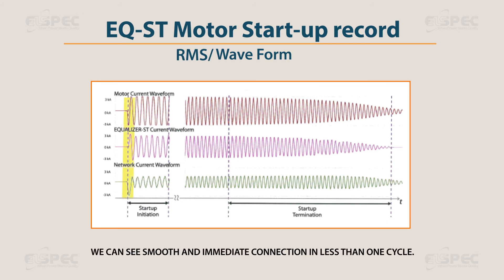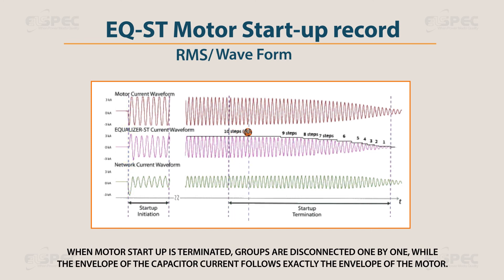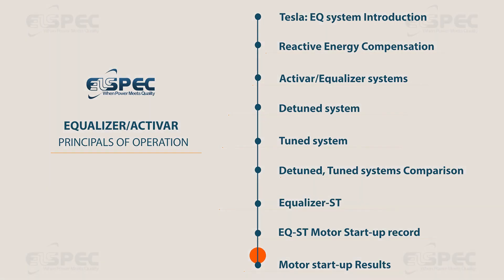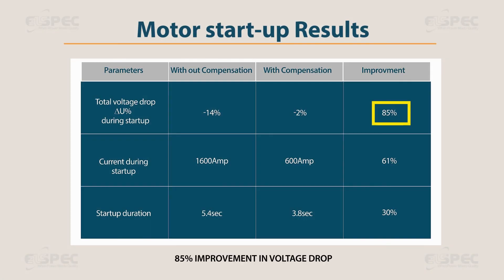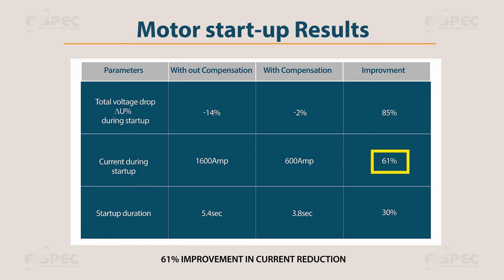We can see smooth and immediate connection in less than one cycle. When motor startup is terminated, groups are disconnected one by one, while the envelope of the capacitor current follows exactly the envelope of the motor. The results: 85% improvement in voltage drop, 61% improvement in current reduction, and 30% reduction in startup duration.